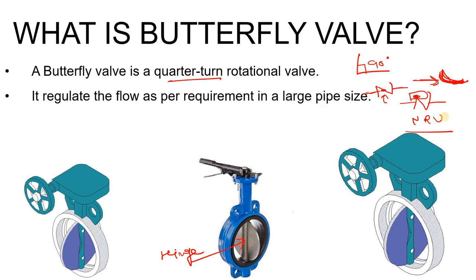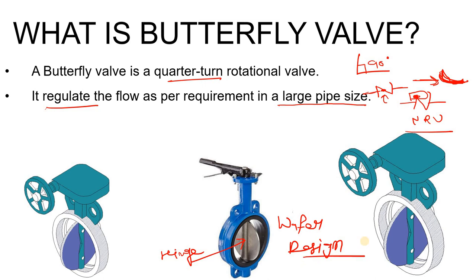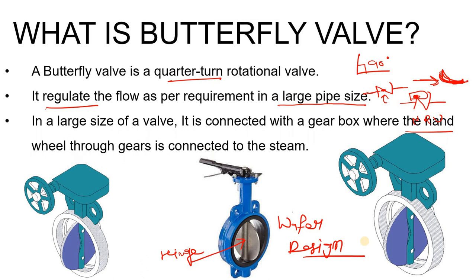The butterfly valve is used to regulate flow as per requirement in large pipeline sizes. We use it in large pipelines because of its wafer design — it is thin, occupies less space, and is less in weight. That is why we mainly use it in cooling water headers. For example, in a urea plant, the cooling water inlet or outlet pipeline will have butterfly valves.